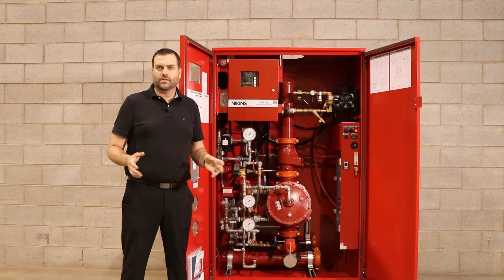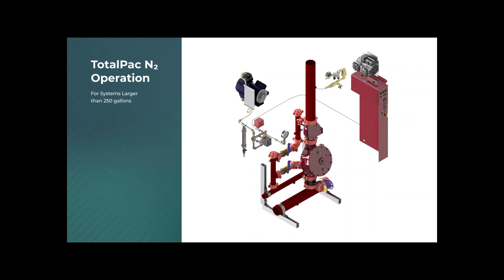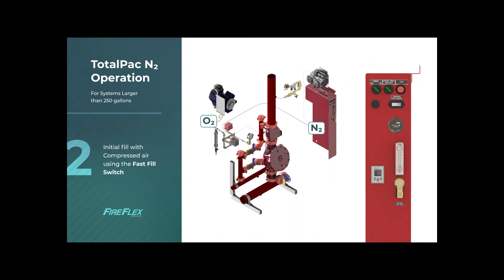In order to see how the system works, let's look at a quick animation. Here is how the TotalPac N2 works for generating and filling the piping network with nitrogen gas. Once the system is installed with the riser connected and power brought to the TotalPac N2 cabinet, simply apply power to the nitrogen generator by turning the power on switch. When the system is in fast fill mode, the air compressor of the dry or pre-action system will automatically start and initially fill the piping network with compressed air. This step is done to fill the piping network rapidly and attain the NFPA requirement of a 30-minute fill time. For systems 250 gallons or smaller, the compressor used with the nitrogen generator achieves the same goal of initial fill with compressed air.